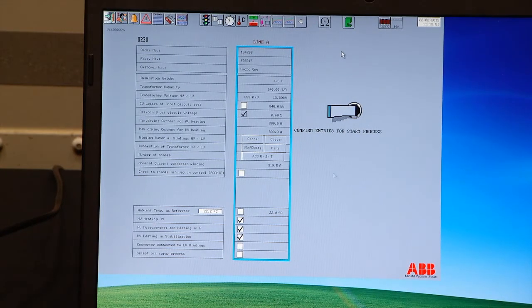When you're done with all the data here, you confirm the entries by clicking this one, saying, okay, the entries are good. I'm satisfied. Normally one guy should enter the data, a second guy should check it. The second guy is then confirming this. And I emphasize once again, the initial temperature is crucial for the whole system to run at the proper temperature readings. That's what we are matching the resistance reading for the initial measurement to.